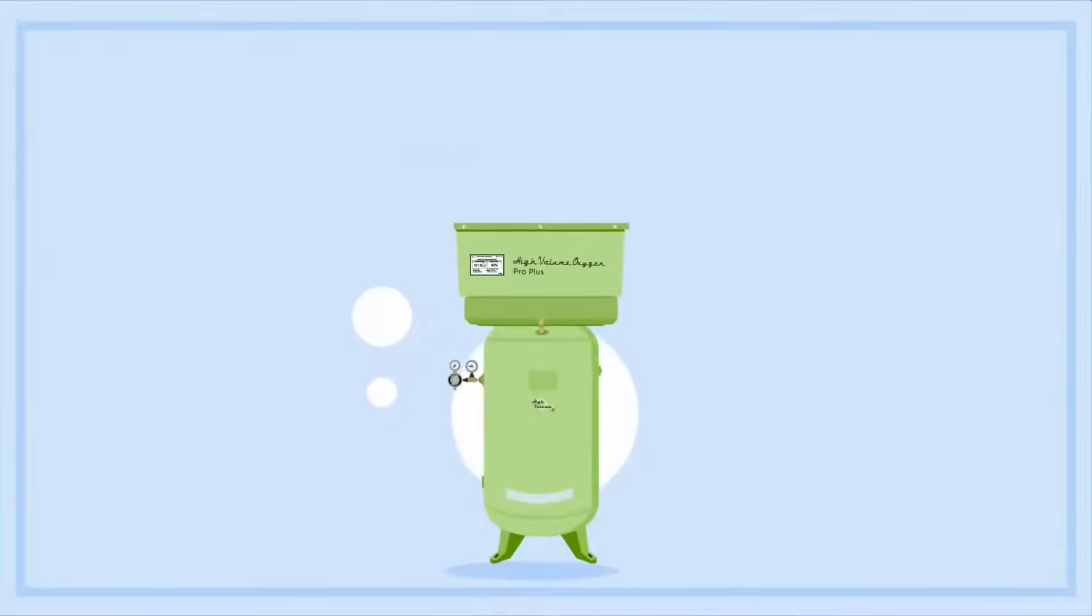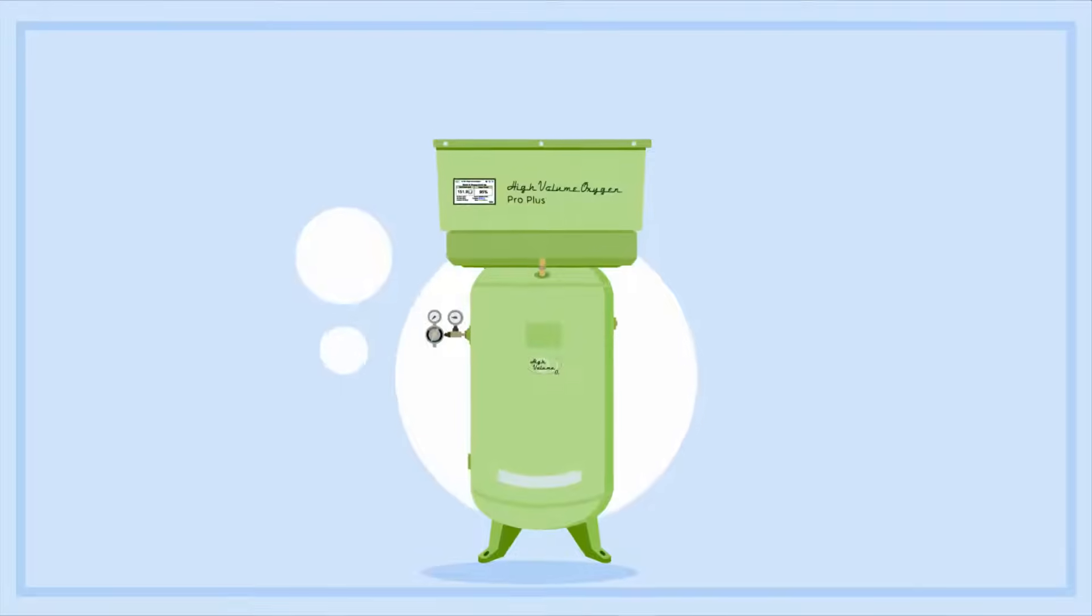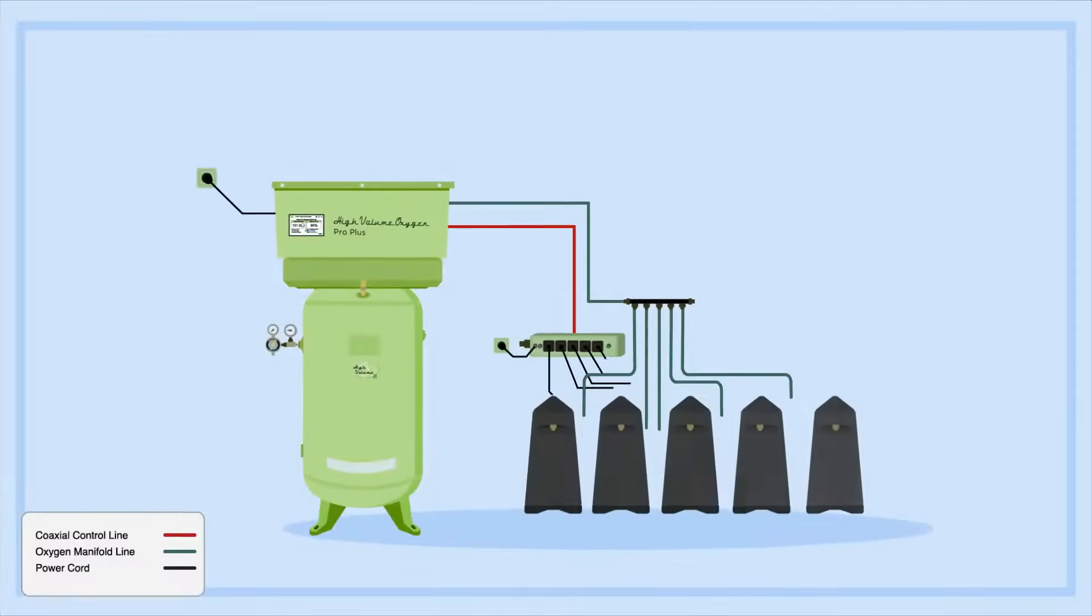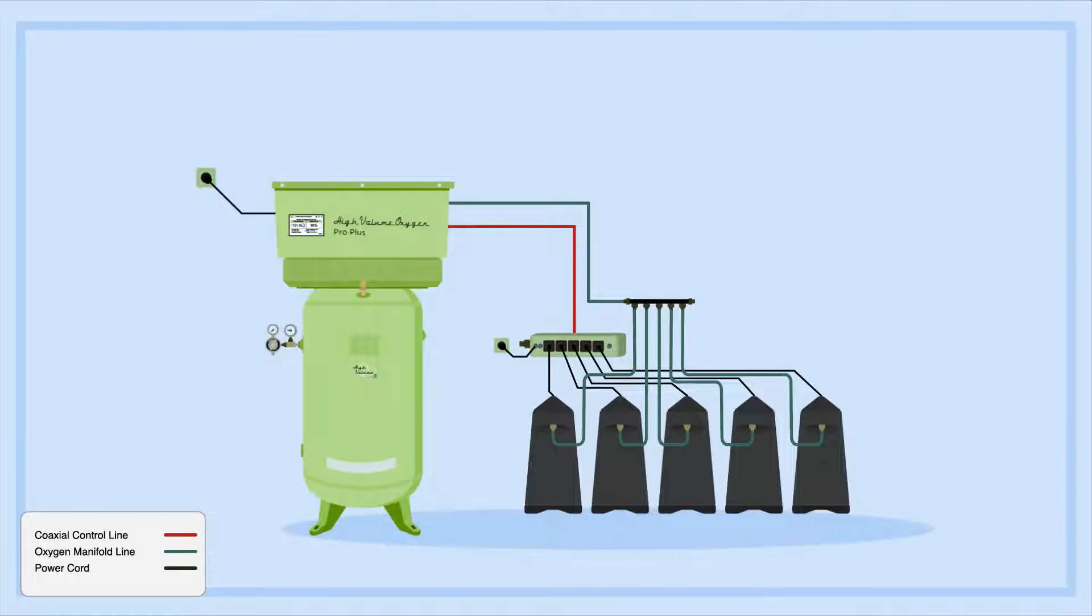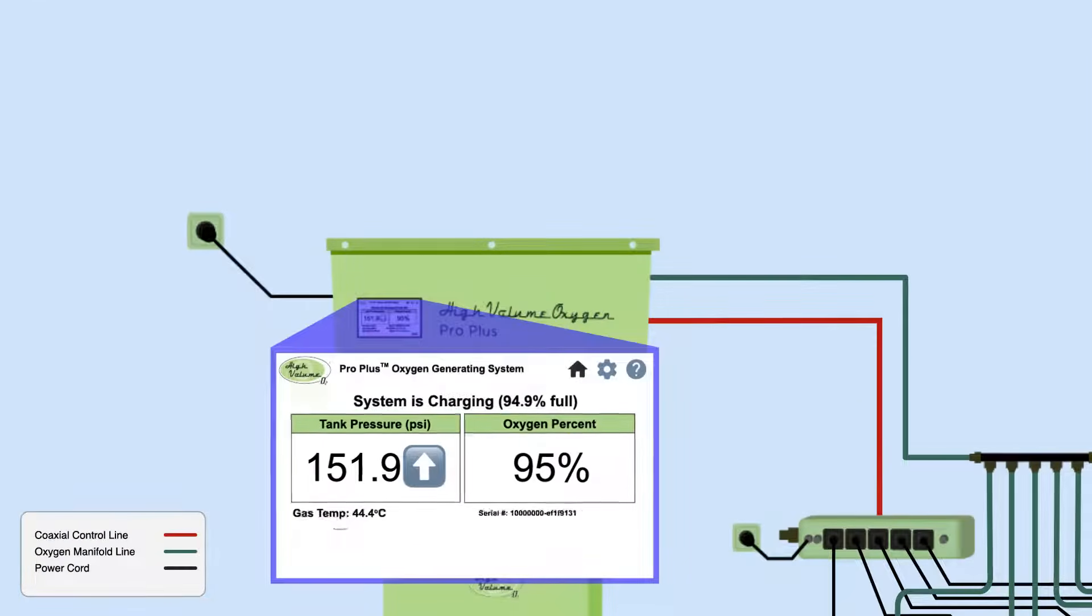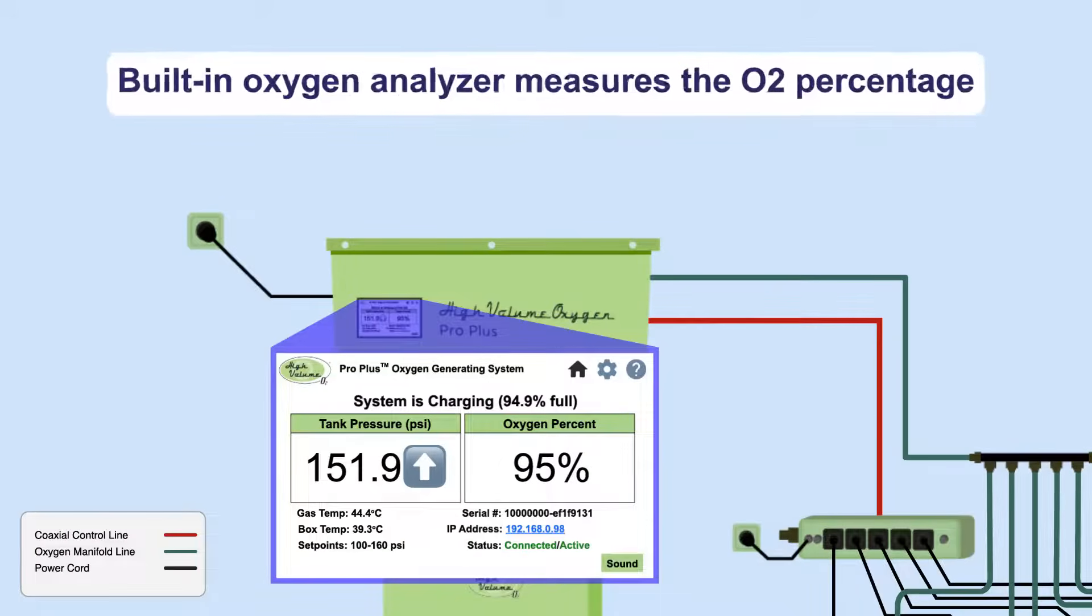The HVO system leverages the combined output of multiple low-cost oxygen concentrators to generate oxygen with a concentration up to 95%. To create a central oxygen-generating resource at your clinic, the accumulated oxygen is pressurized, stored, and monitored.